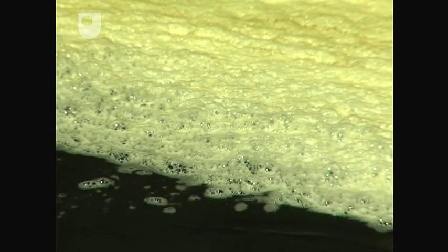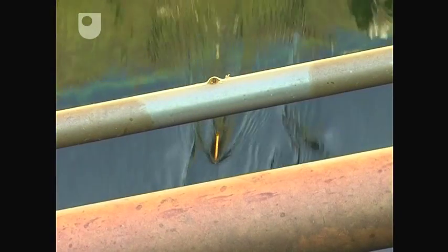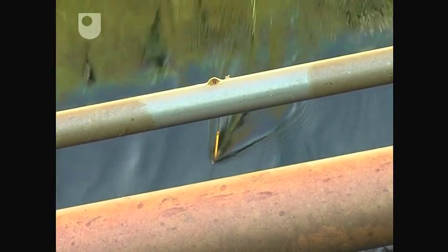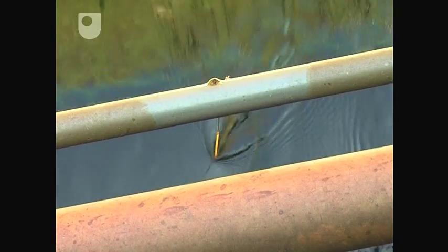The starches released from the dead algal cells form a scum on the water surface. The water, along with the scum, is then dosed with ferric sulphate to bring the dead algal cells together within flocs of ferric hydroxide.